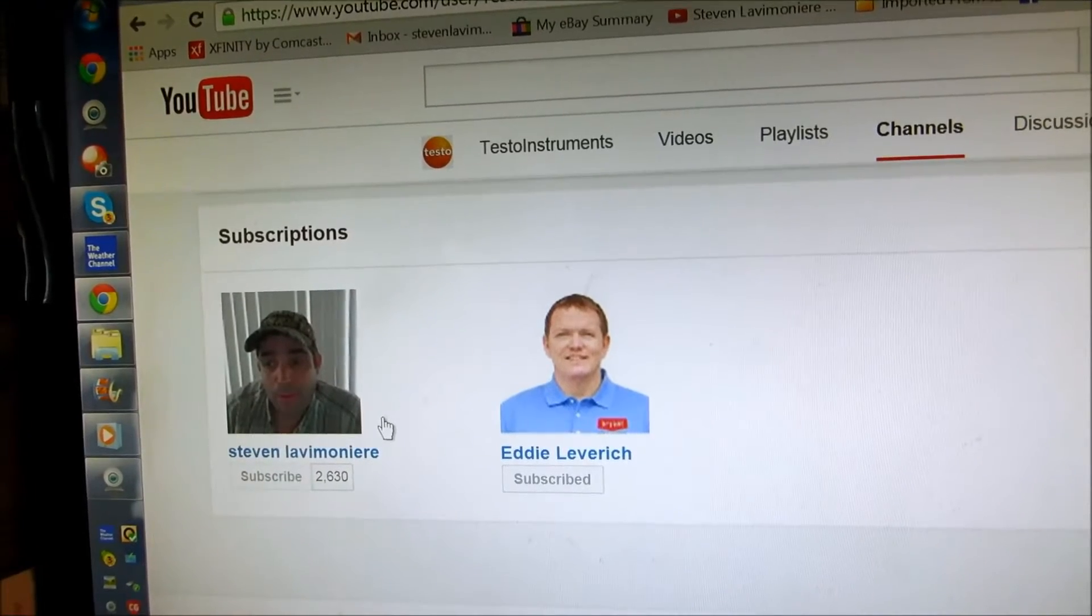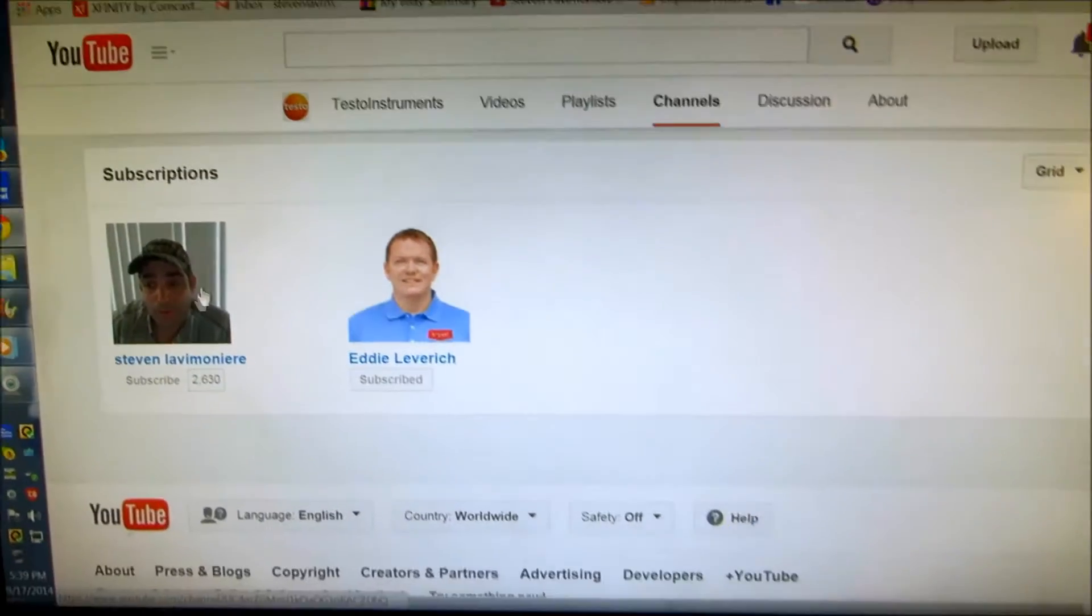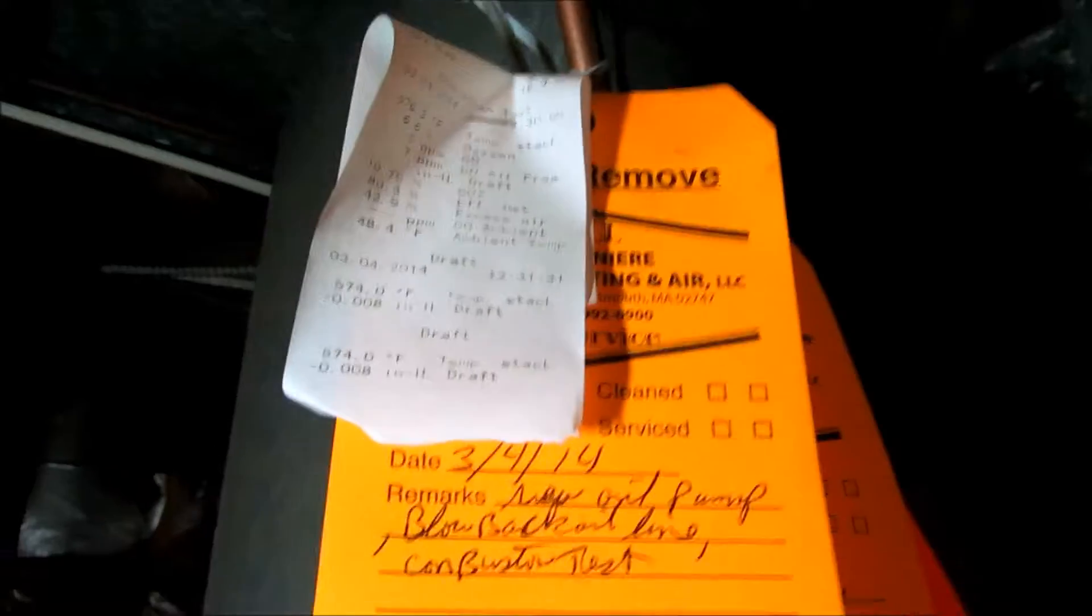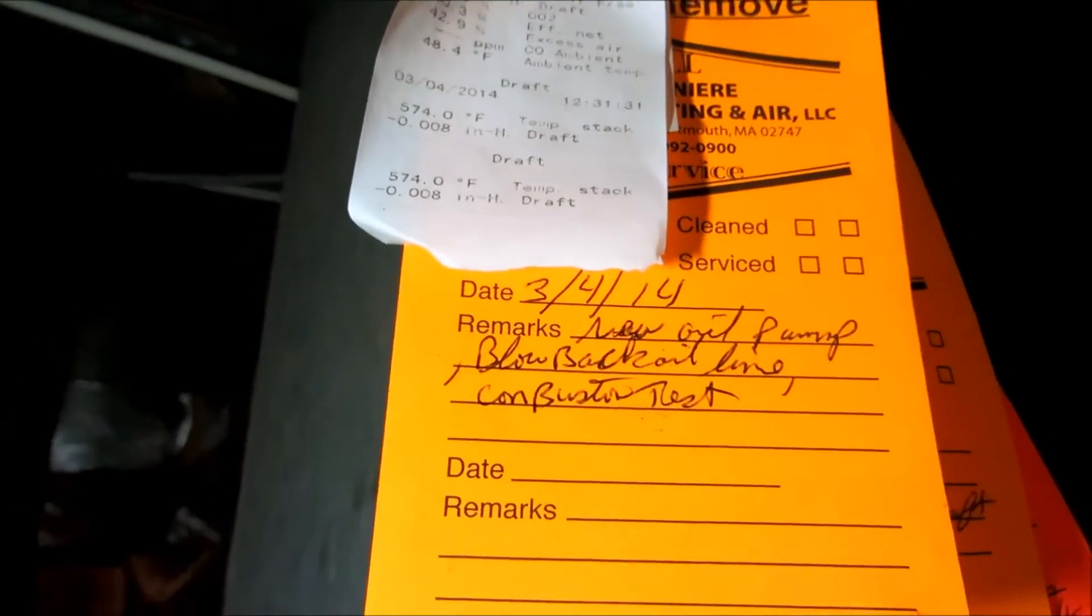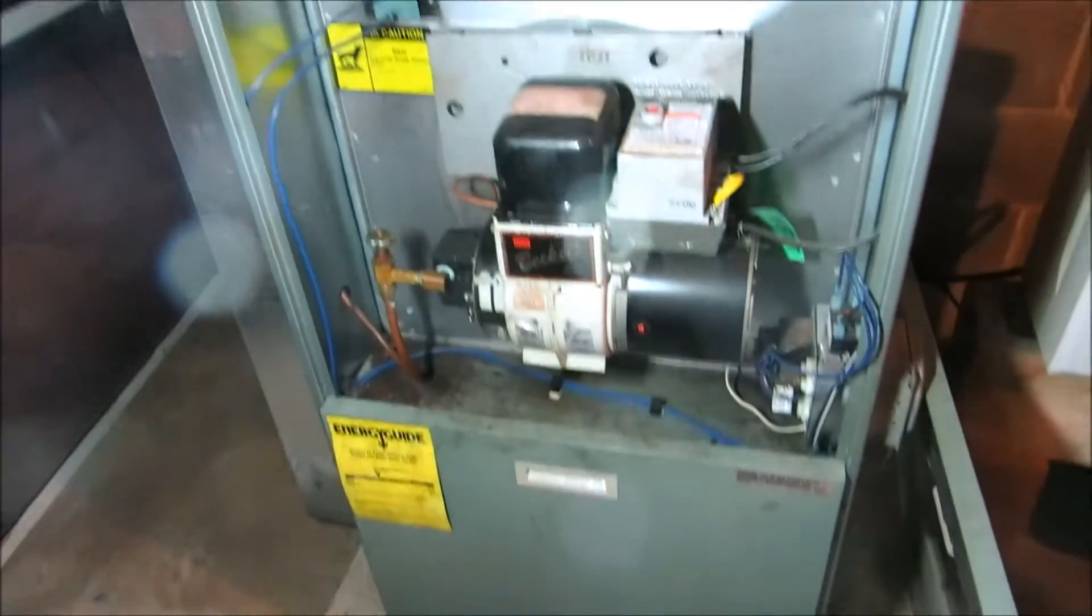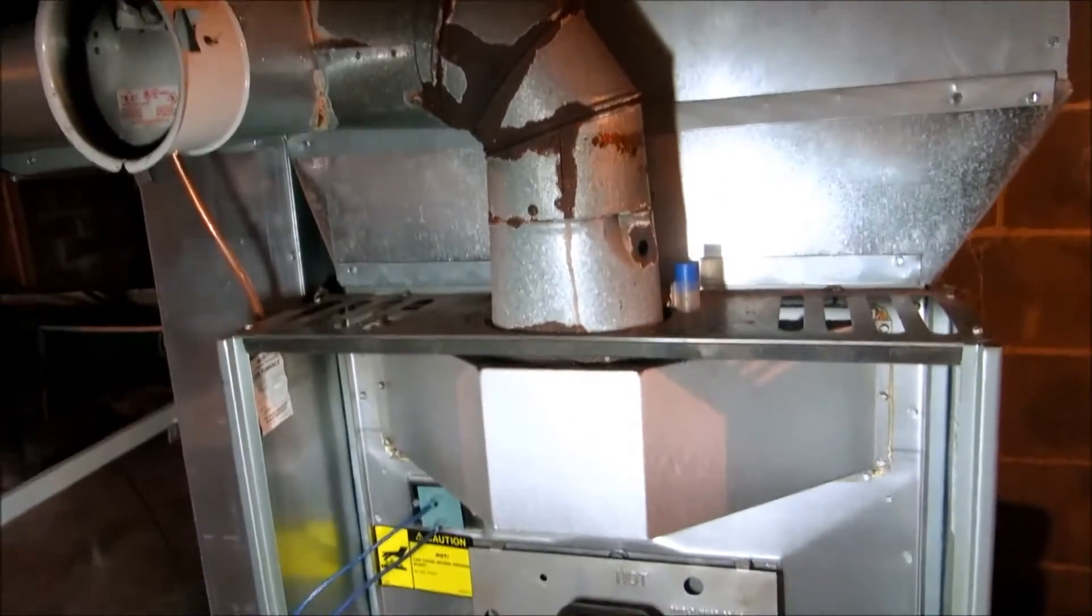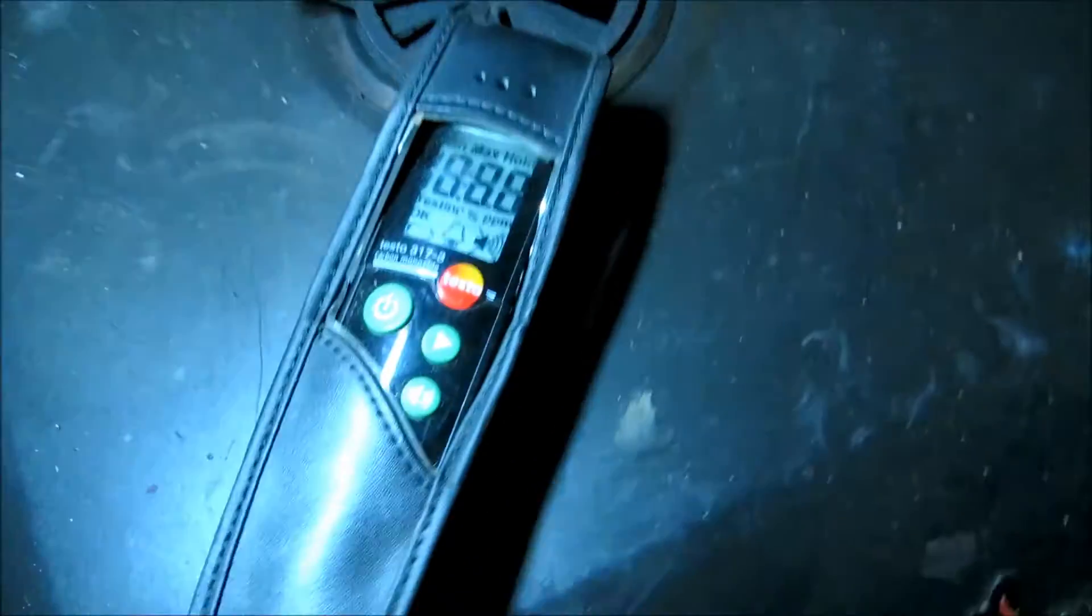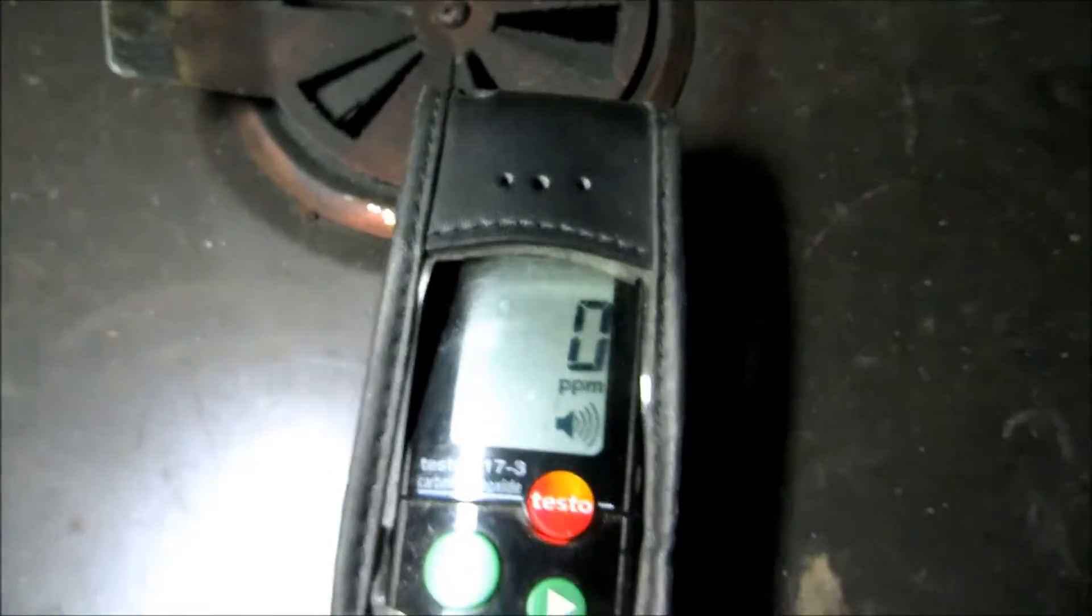Alright guys, I was here like six months ago, did a cleaning on it. Lady's renting out the house and she wants me to check it, so I'm going to check the combustion, put my Testo on here and check the combustion with the Testo 320. I can fire it up down here.